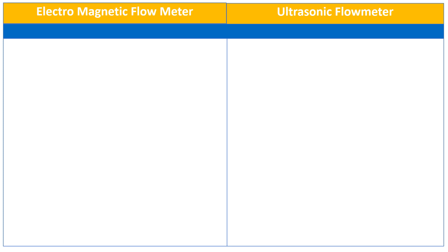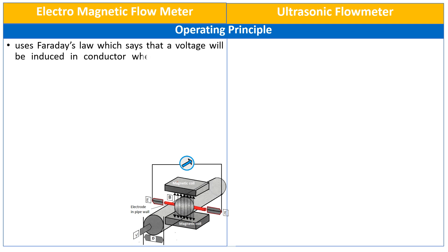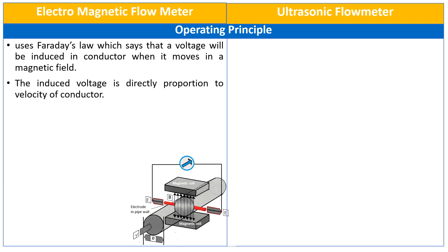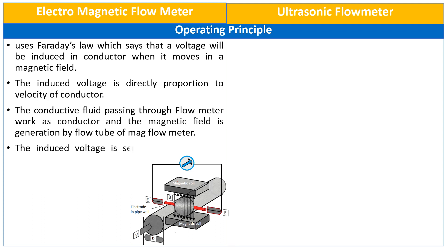First of all, we will talk about the operating principle of both the flow meters. In electromagnetic flow meters, it uses Faraday's law, which says that a voltage will be induced in a conductor when it moves in a magnetic field. The induced voltage is directly proportional to the velocity of the conductor. The conductive fluid passing through the flow meter works as a conductor, and the magnetic field is generated by the flow tube of the flow meter. The induced voltage is sensed by the sensing electrodes fitted inside the flow tube.